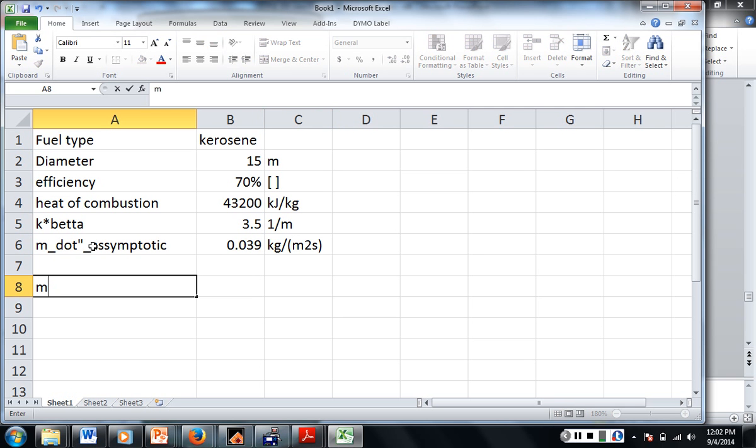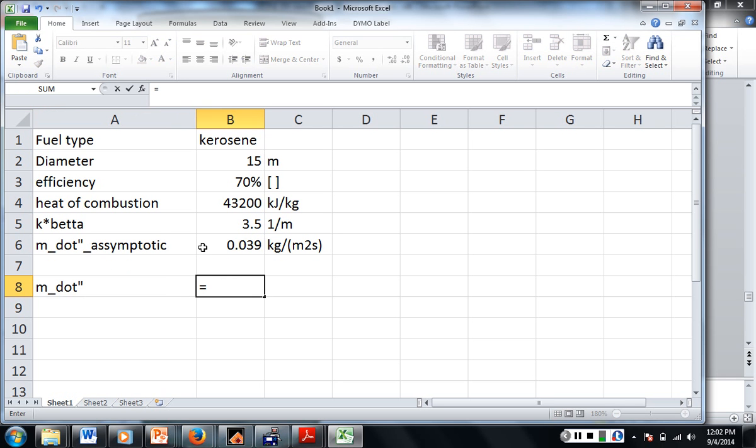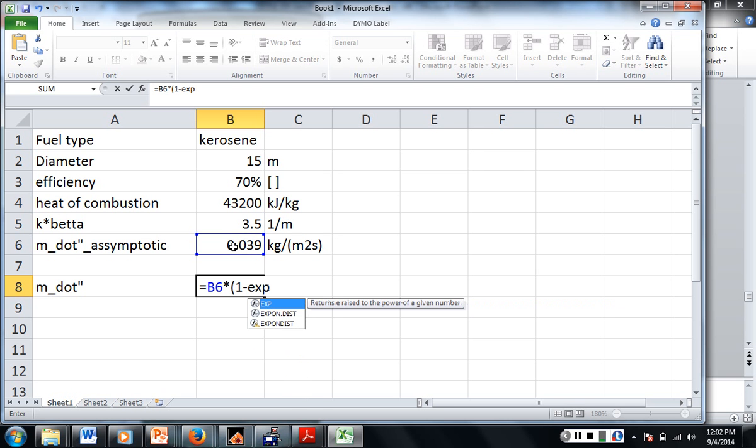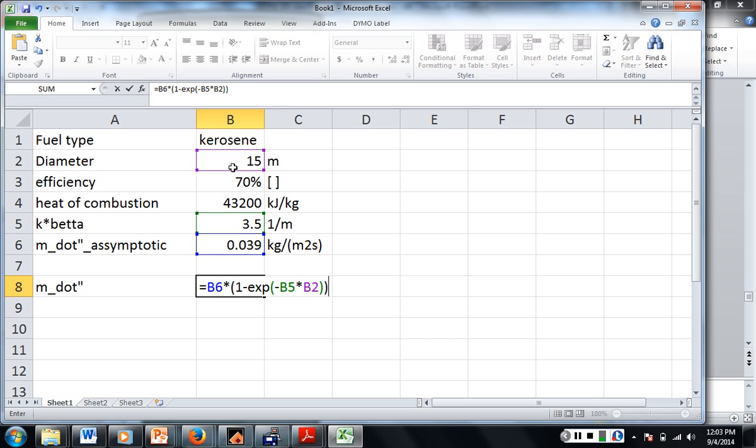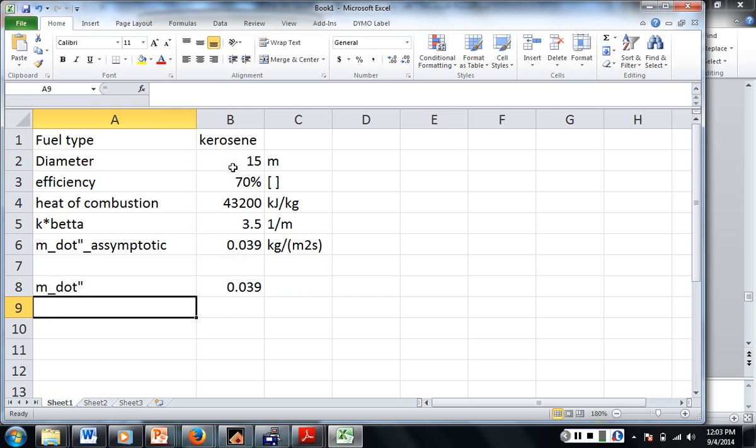So then our m dot double prime for this particular case is going to be equal to our asymptotic mass flux times the quantity 1 minus... In Excel, exponential, exponential, exponential, parenthesis, negative k beta times our diameter. It's 15 meters. And we're going to close that first parenthesis, close the second parenthesis, and we should be done. Theoretically. Now it should be very similar to our asymptotic mass flux rate because it's a large diameter fire. So it is. It's the same. Alright. So that's good.